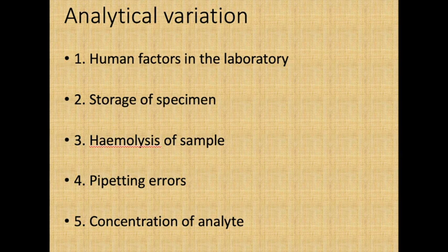Analytical variation is very much dependent on the concentration of the analyte we want to measure. The lower the concentration of the analyte, the greater is the analytical variation.